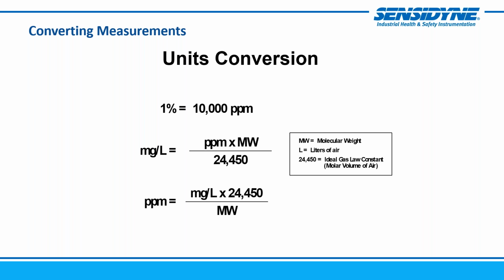There are times when a detector tube might not be in the unit of measurement that you need for compliance or for your testing parameters. So for those that aren't aware, when you see a concentration of 1%, 1% is equivalent of 10,000 parts per million. To get from a ppm scale to a milligrams per liter scale, you would use this formula where you multiply that reading in parts per million times the molecular weight of that gas in question, and you would divide it by 24,450. And of course, you can invert that formula if you were going the opposite direction from milligrams per liter to parts per million.